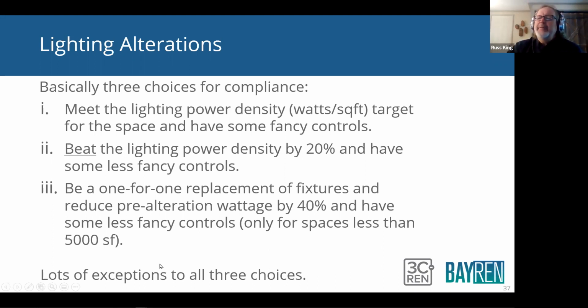So if you're doing a complete relamping or replacing all the fixtures, this option three here is you can do that. It only applies to spaces less than 5,000 square feet is one important trigger though. But if you're just doing like we talked about these TIs where they're adding some office spaces or stuff like that, you're probably going to have to hit one of these two up here above. Either meet the power density requirement and have some fancy controls, or beat the power density requirement by 20% and not have to have those fancy controls, okay?